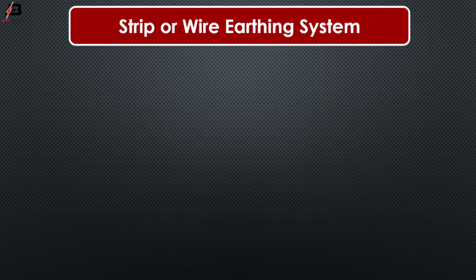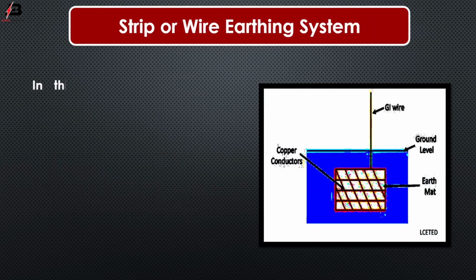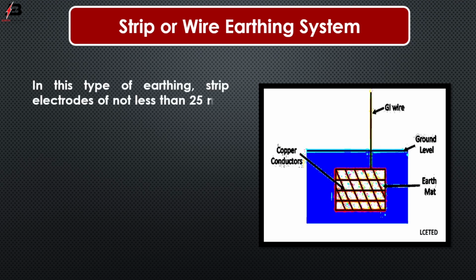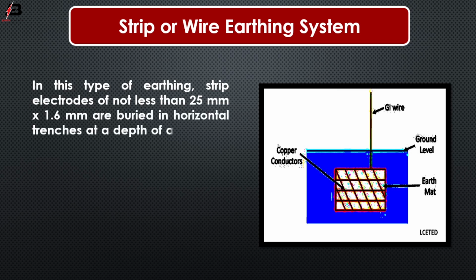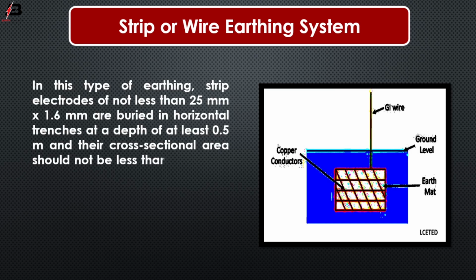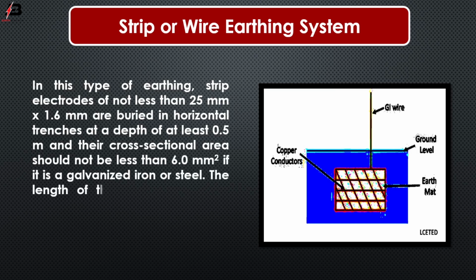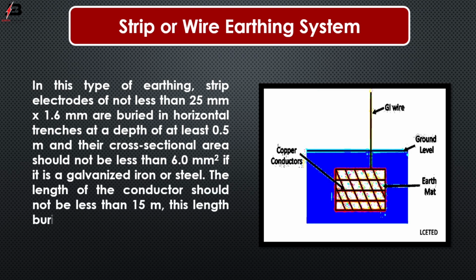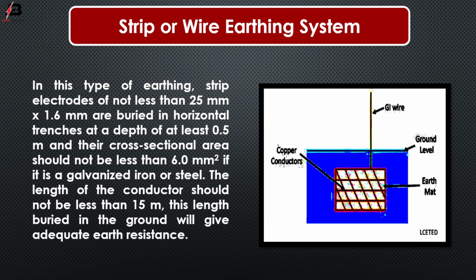Strip or wire earthing system. In this type of earthing, strip electrodes of not less than 25 mm by 1.6 mm are buried at least 0.5 m deep, and their cross-sectional area should not be less than 6.0 mm square. If it is galvanized iron or steel, the length of the conductor should not be less than 15 meters. This length buried in the ground will give adequate earth resistance.